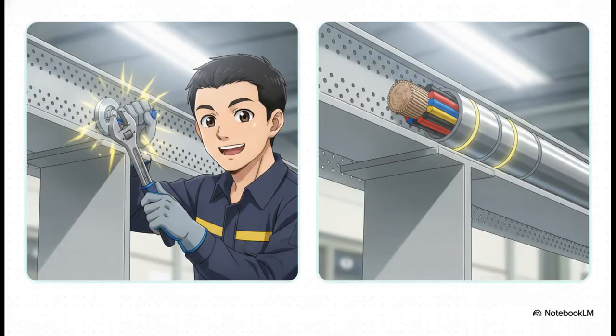So the crucial point is, how do we actually satisfy this bonding requirement? Well, the code says a tray is deemed to be bonded if the metal supports are bolted to the tray and are in good electrical contact with the grounded structural metal frame of the building itself. Alternatively, you can actually skip bonding the tray entirely, as an exception, if absolutely every single cable contained within that tray has an interlocking metal armor or a continuous metal sheath that's permitted to be used as a bonding method.